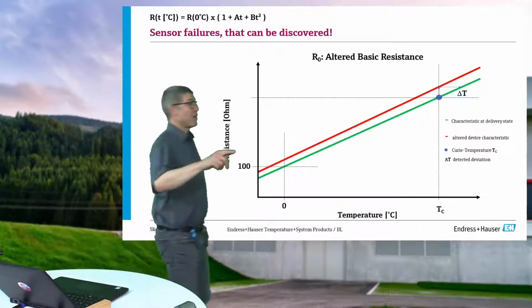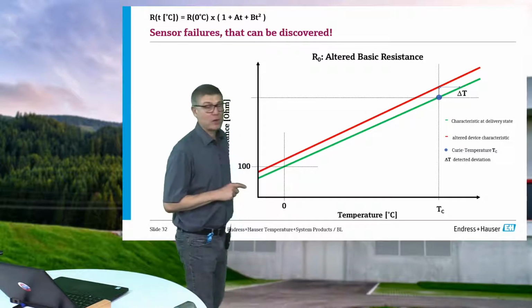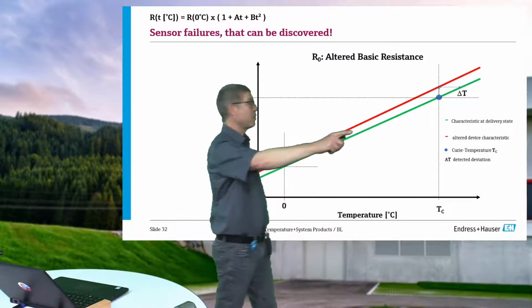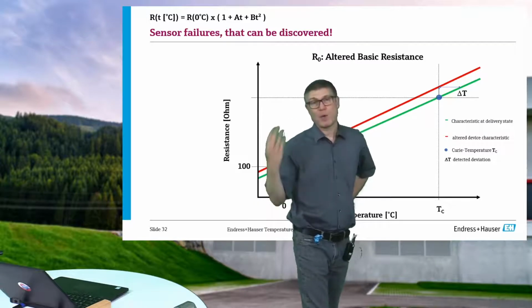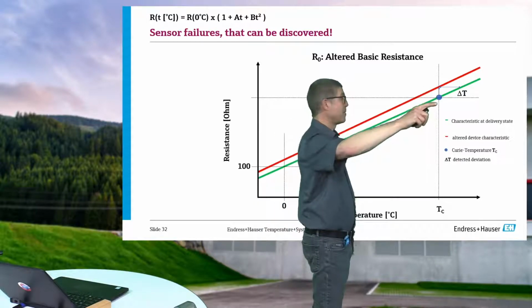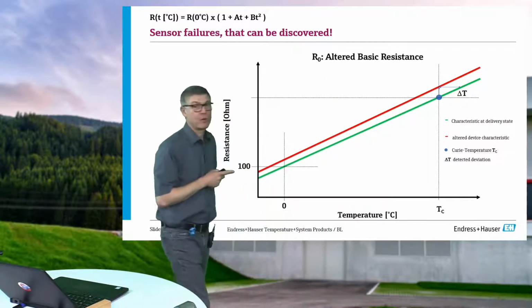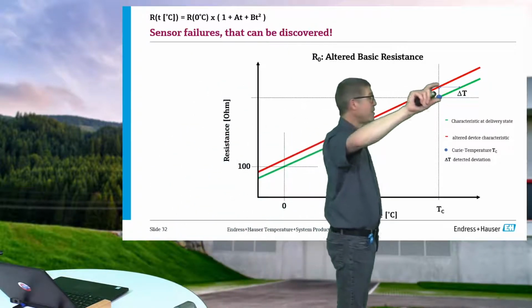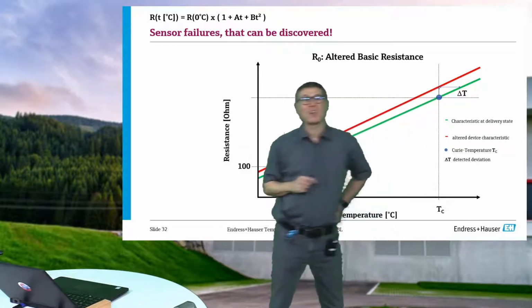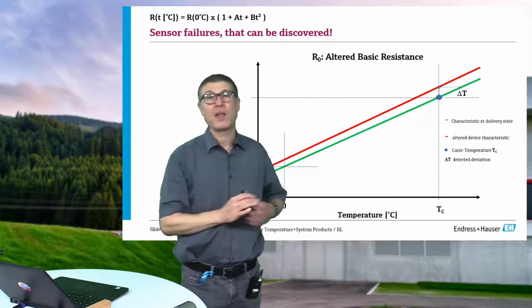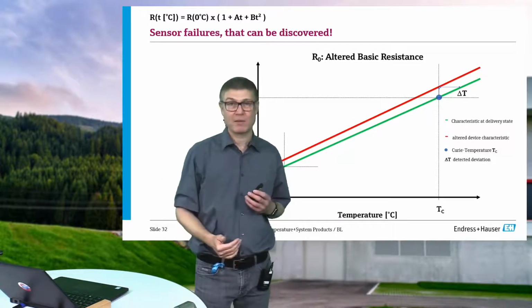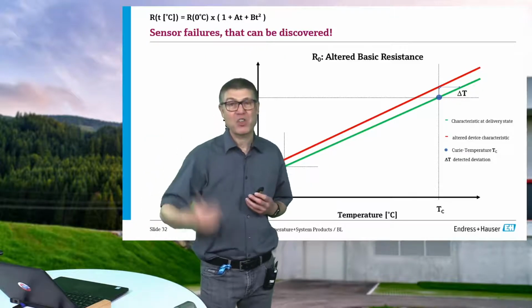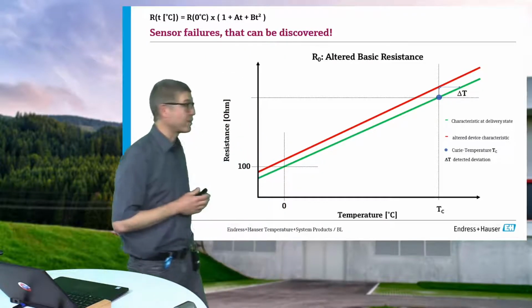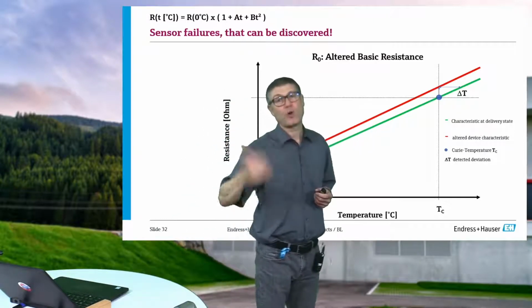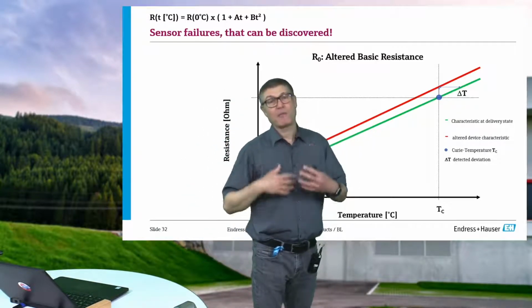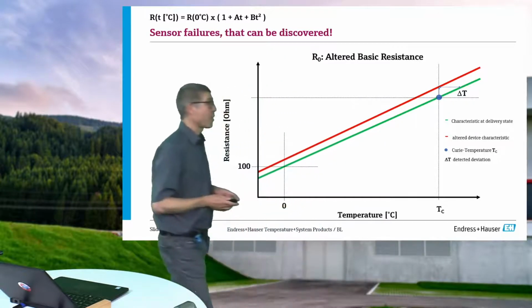And so what the automatic calibration usually does is, if the new sensor, the green curve, has changed by mechanical shock or thermal shock, the complete curve is at a different position. And if we see a difference at 118 degrees, the sensor cannot be accurate somewhere else, and you will get an alarm and it will stop your plant. So you won't have other batches affected. That is the general idea of this concept. And so that makes it possible to prolong your calibration intervals without having additional risk.